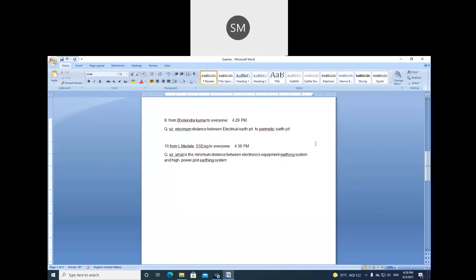You can try to provide an earth mat. Is it possible to put an earth mat? We have done this at times, providing an earth mat of a particular size to get the required value. We cannot dig vertically because of the geographical conditions of the area, so we have gone horizontally. If you cannot go vertically, the answer is to go horizontally. Earth electrodes should be provided horizontally, at least 0.6 meters below the ground.